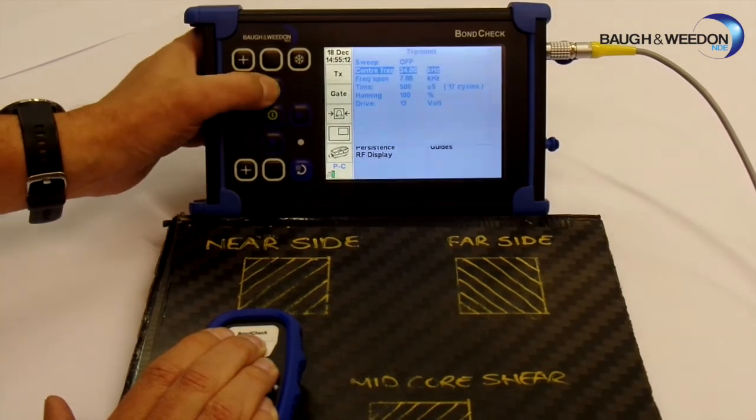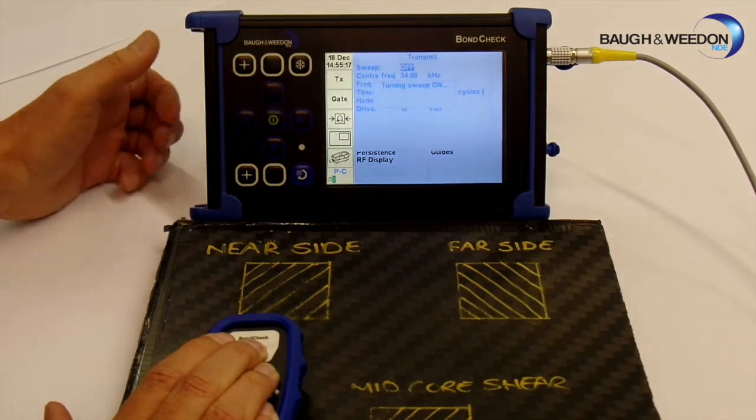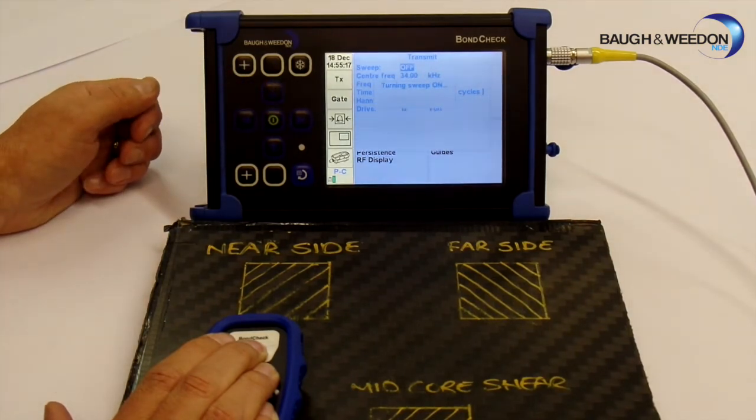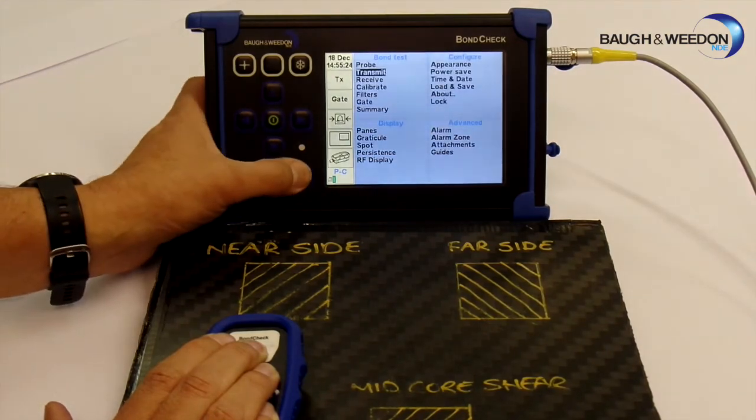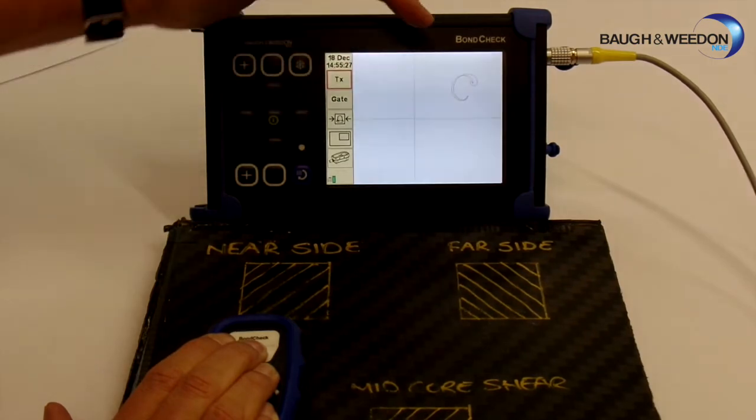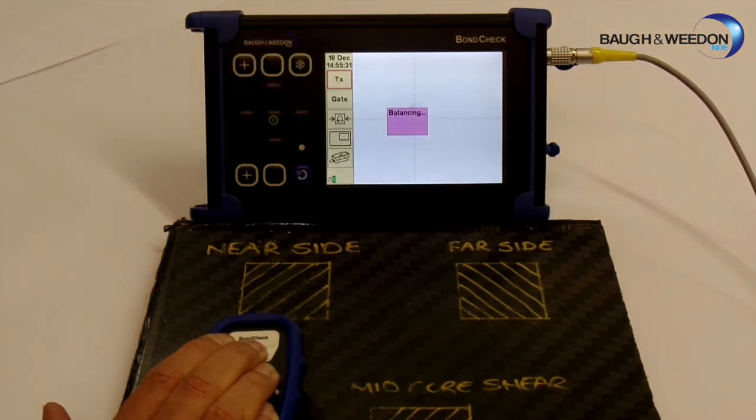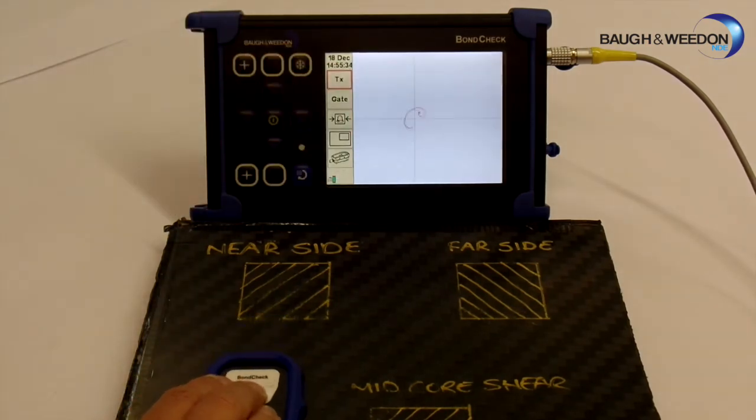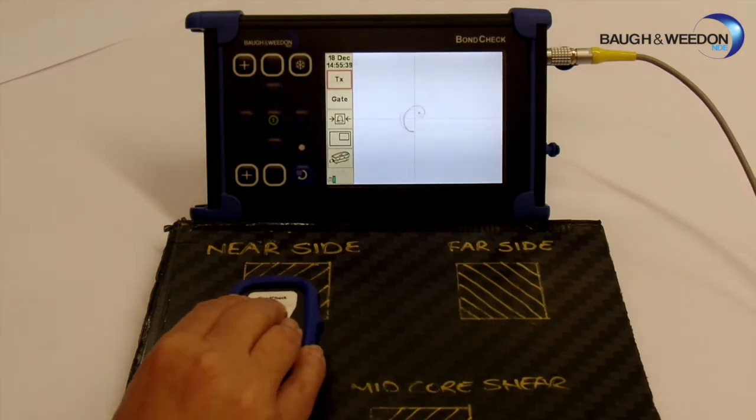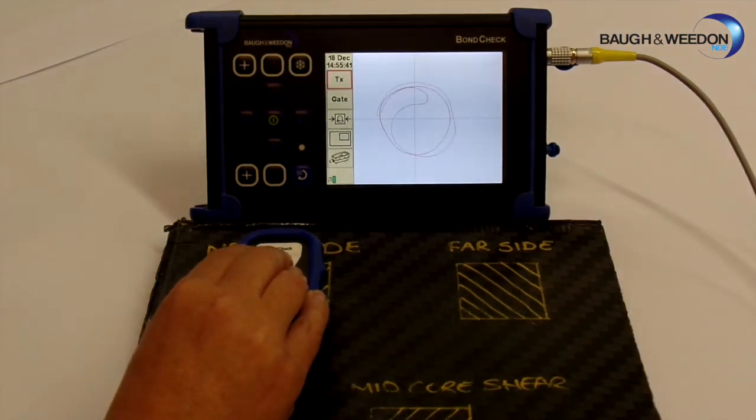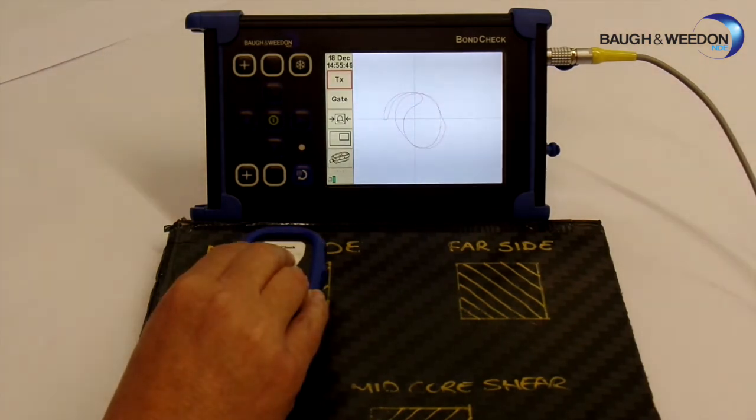So now select that, go up to sweep on and off, select it, turn sweep on. Sweep has now been turned on, we can come out of here. We're now going to the sweep display. You'll now see we've got a strange letter C appeared. If I balance it, we'll bring it back to the center of the screen. So now if we scan, it sort of does a bit of changing, but as we go over the defect, there's a huge change. Very obvious that we're on the defect.